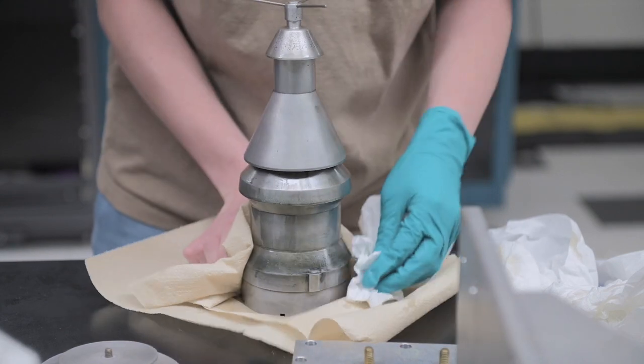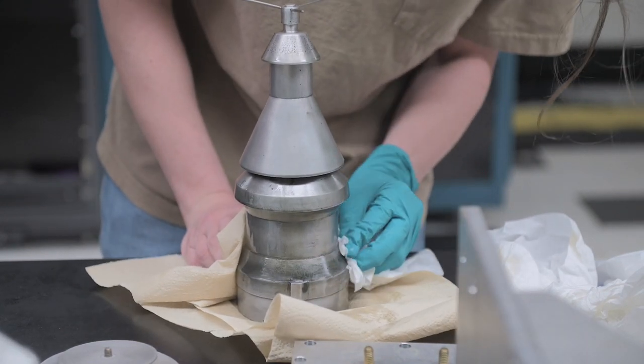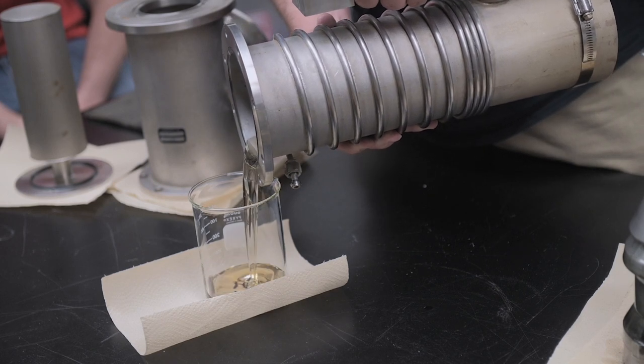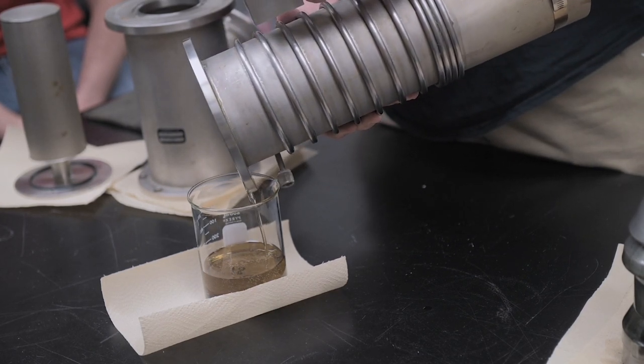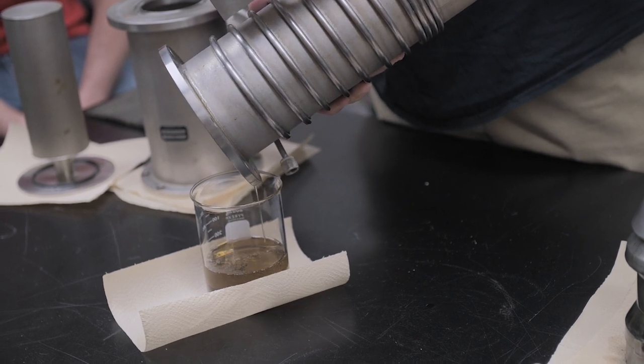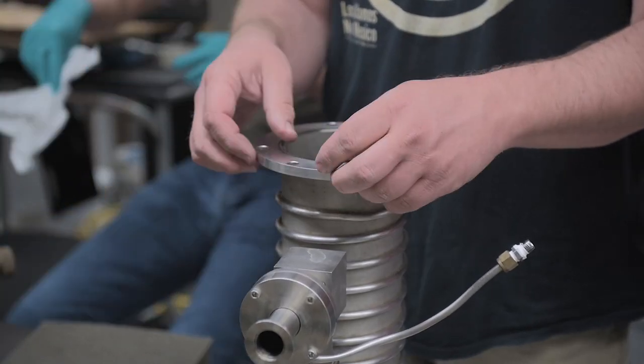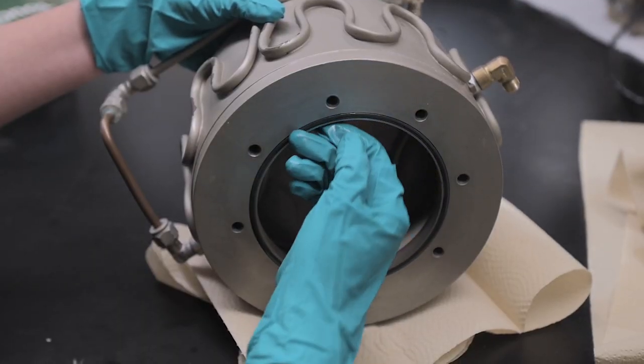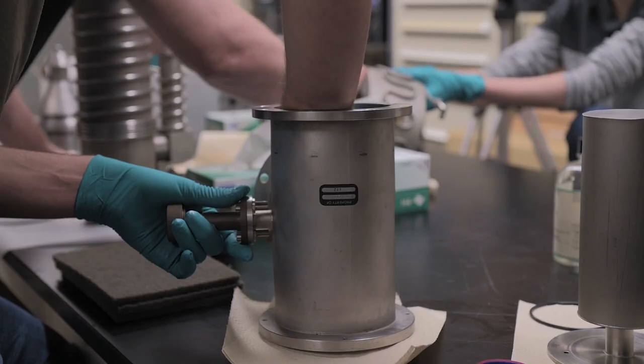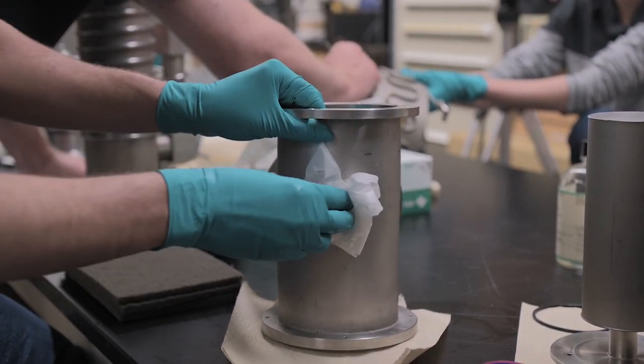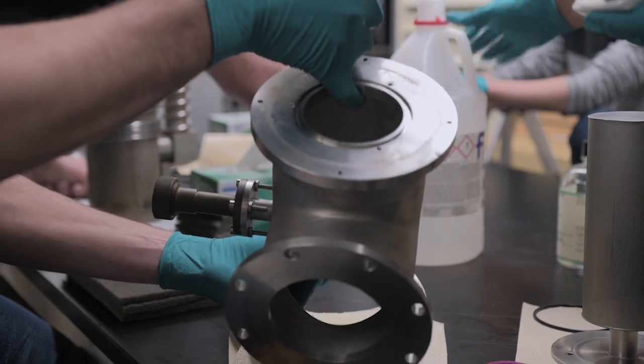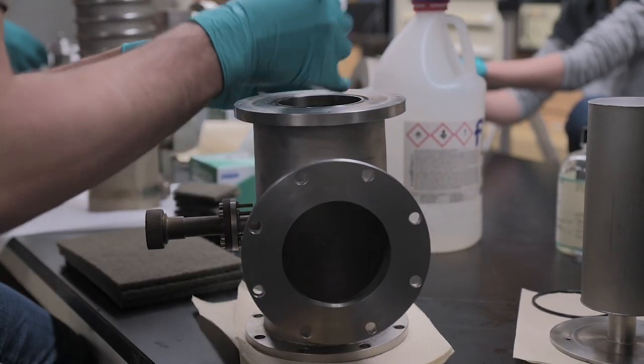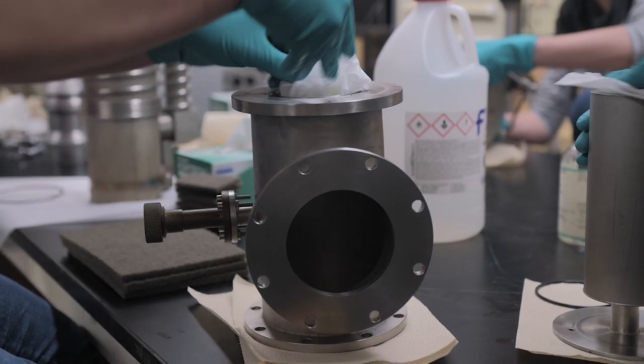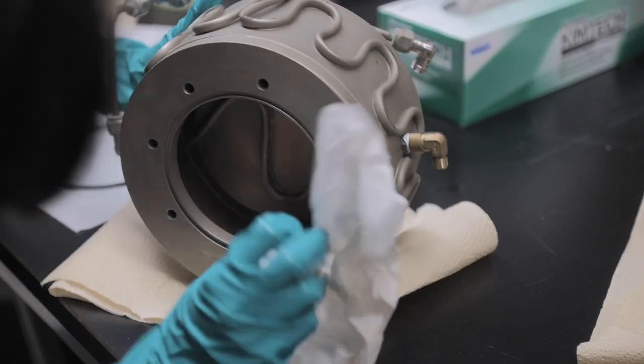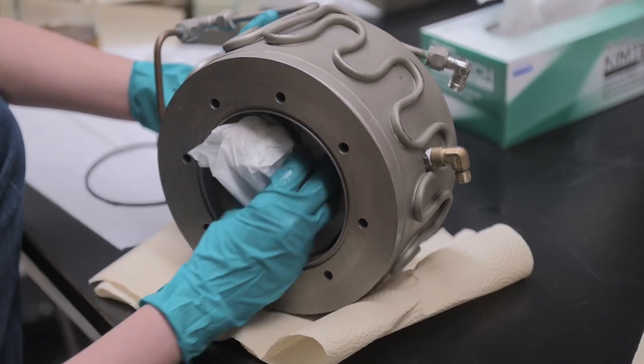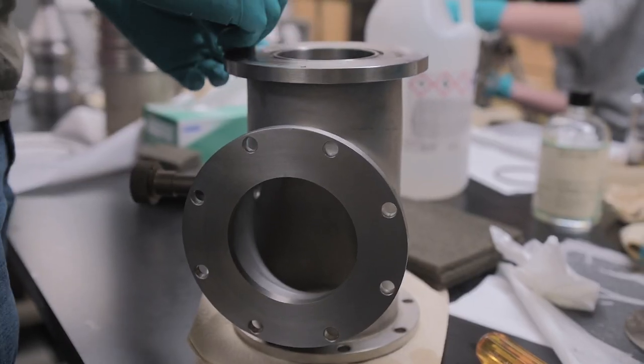Here, solvents like acetone and lint-free Kim wipes are being used to slowly remove the caked on diffusion pump oil. The old diffusion pump oil is then drained from the main body of the diffusion pump. The O-rings are then removed from all parts so that they can be replaced with fresh O-rings. Similarly, the inside of the cold trap is cleaned of any condensed diffusion pump oil. The water-cooled baffle is also likewise cleaned of any spare diffusion pump oil.